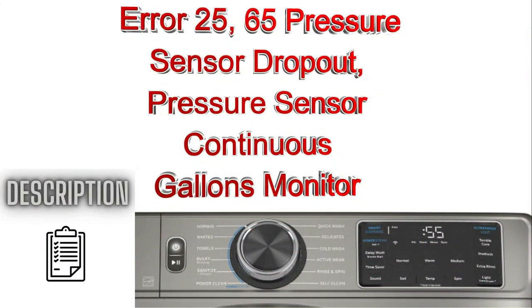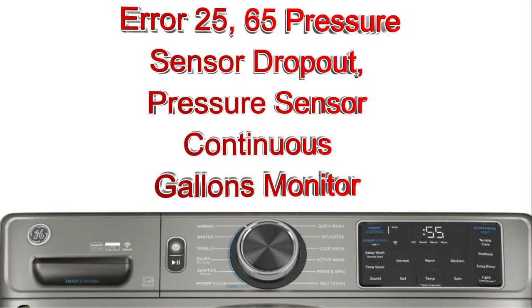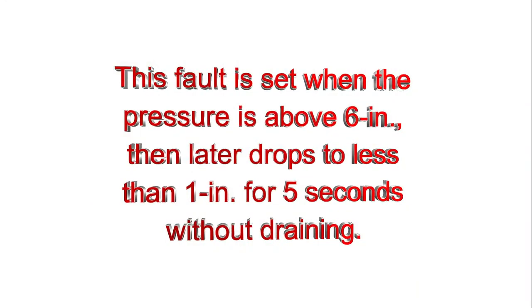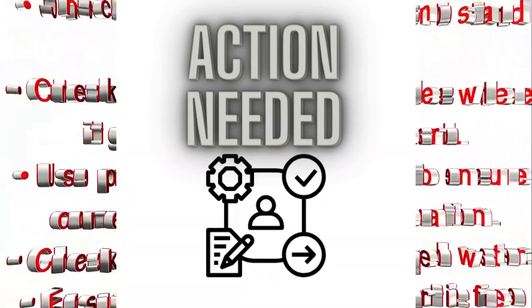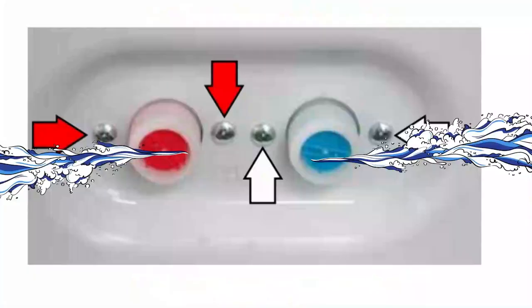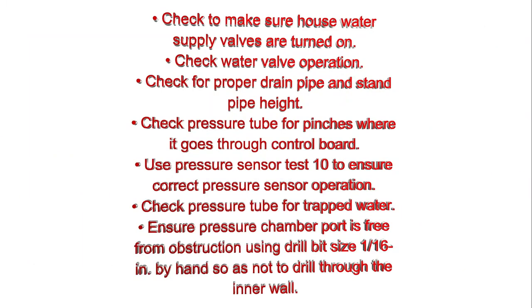Error 25, 65, pressure sensor, dropout pressure sensor, continuous gallons monitor. This fault is set when the pressure is above 6 in, then later drops to less than 1 in, for 5 seconds without draining. Check to make sure house water supply valves are turned on. Check water valve operation. Check for proper drain pipe and stand pipe height.